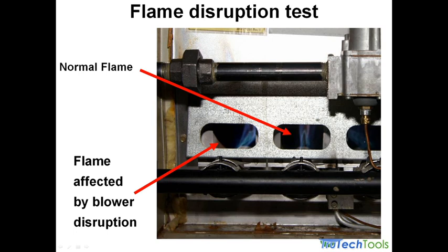Somebody was going to ask me here, I'm sure, right here by the thermocouple, what's this on the side here? That's a pilot that you're seeing. That's the other angled flame you're seeing. But this one here on the left, that's flame impingement.